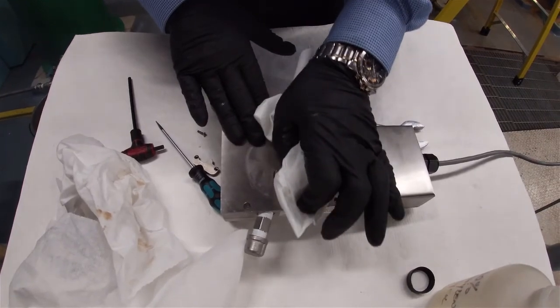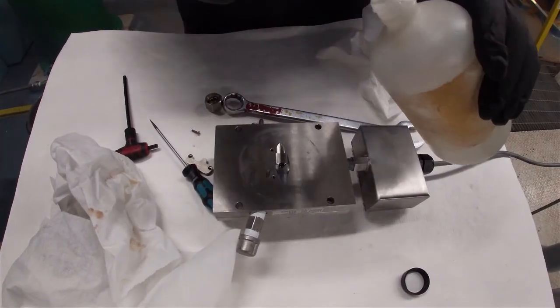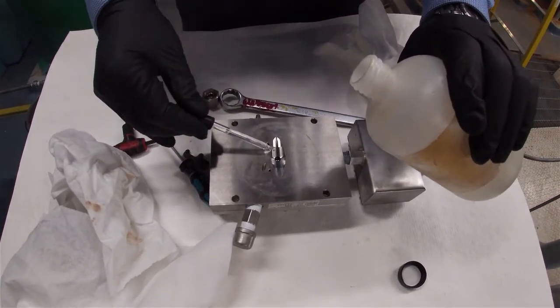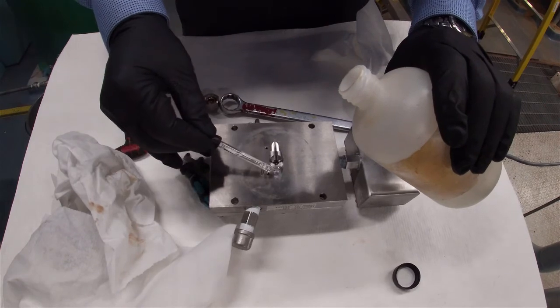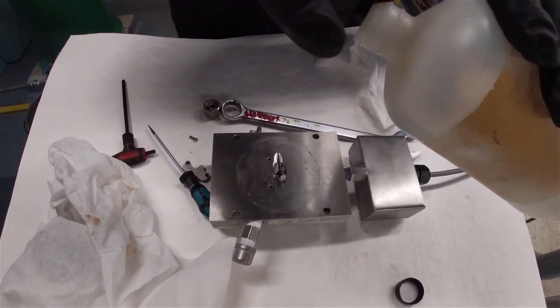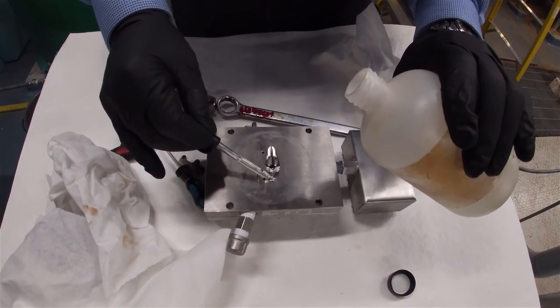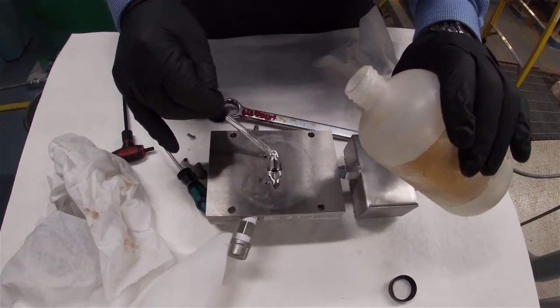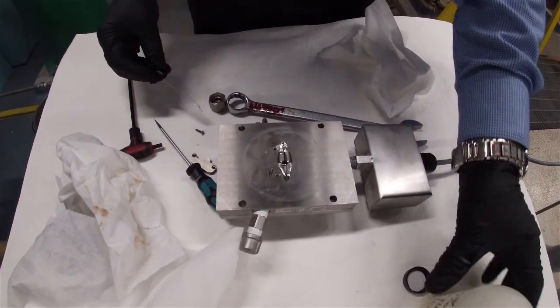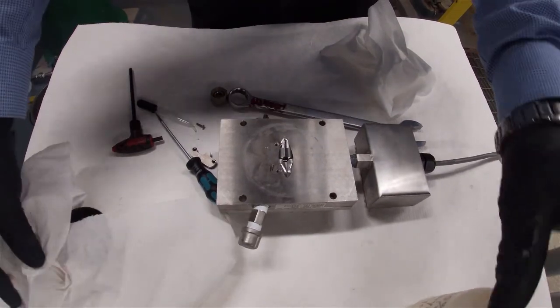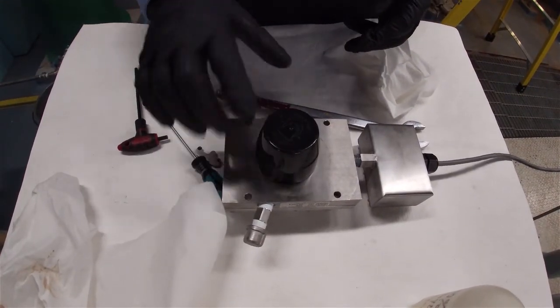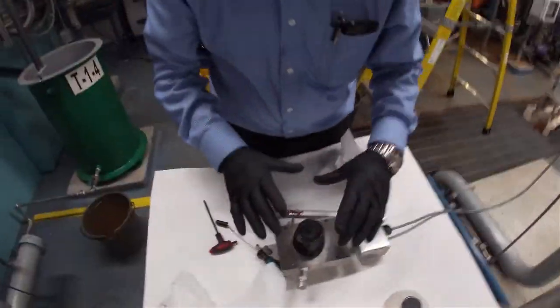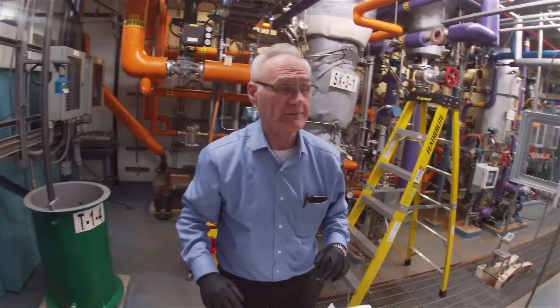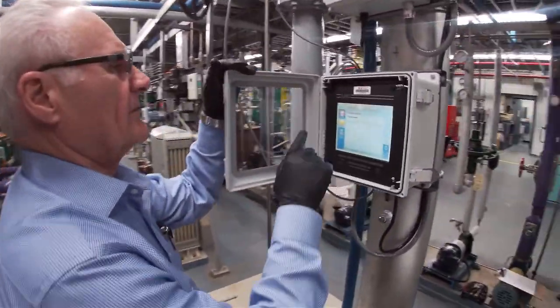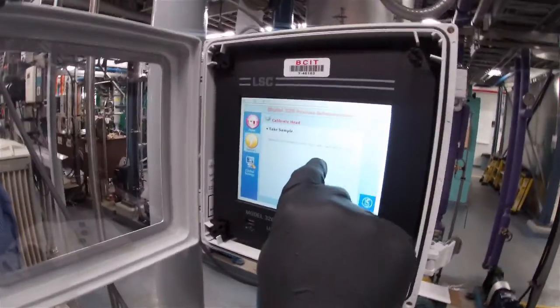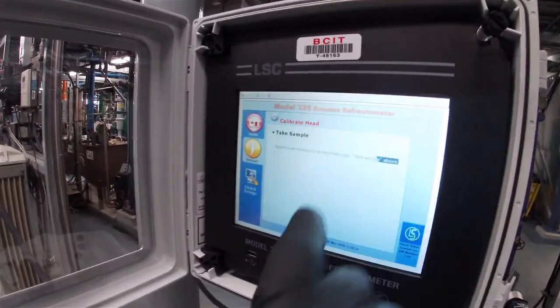I've done a good wipe job on that. Take another sample, put it on. You've got to fill this whole space up so that you don't end up losing signal that might be refracted away. Okay, so now the next thing we're going to do is cover that up with a black body, just a cap off of a spray can of paint, but that keeps any external light from coming in and disturbing it. All right, so now I have applied the known sample, and then it says click take sample above. So I'm going to do that, I think.